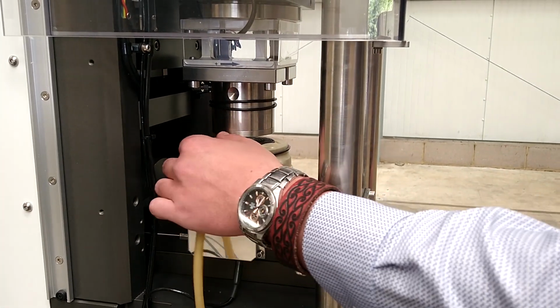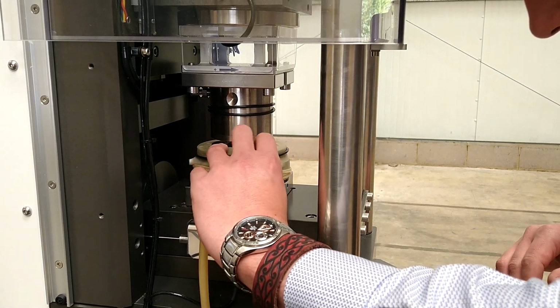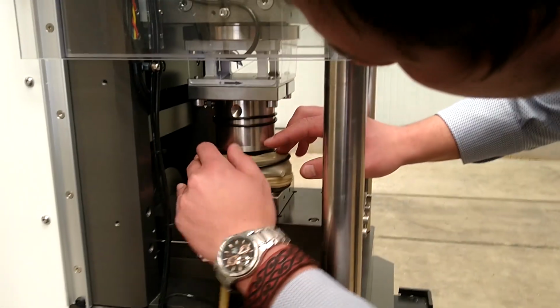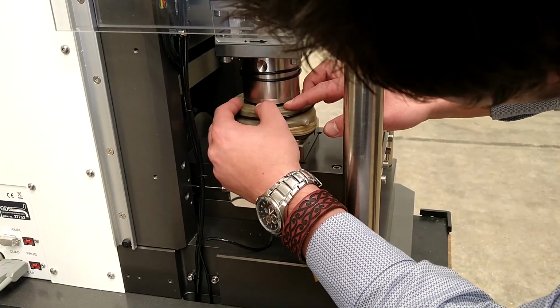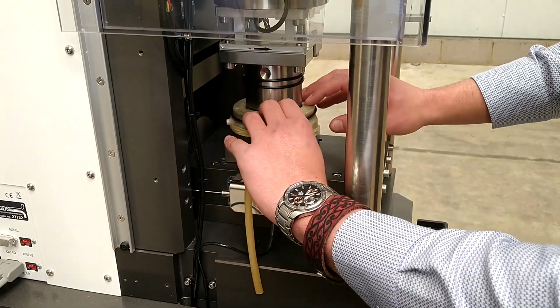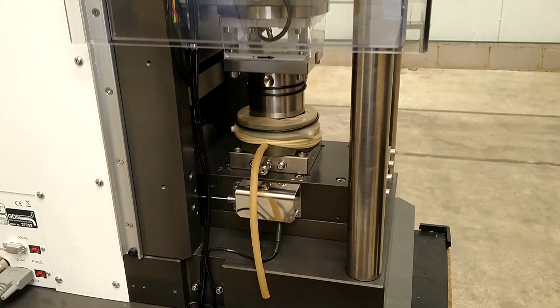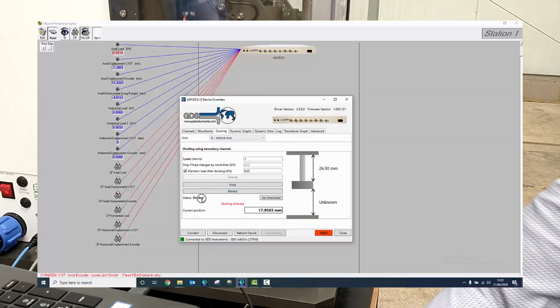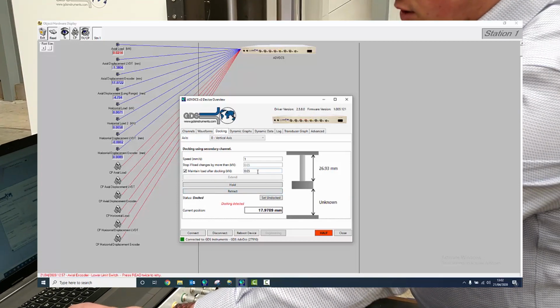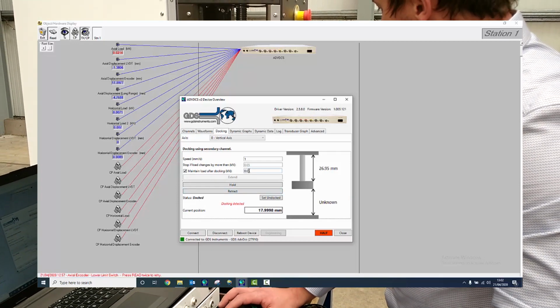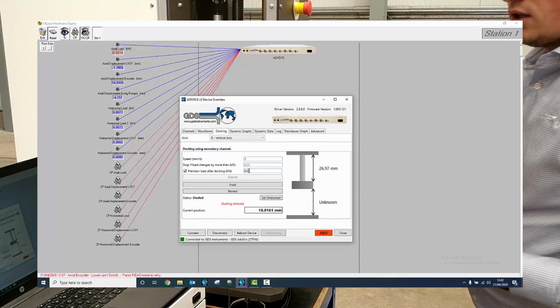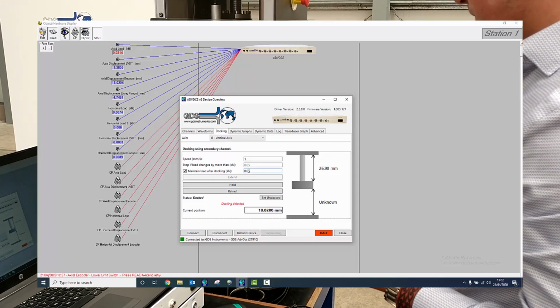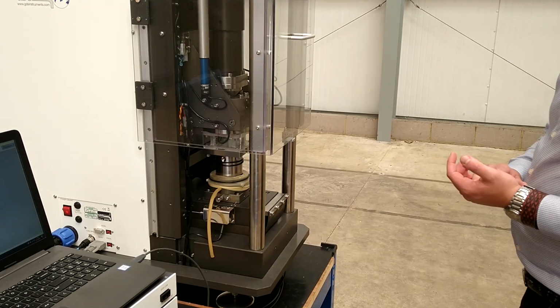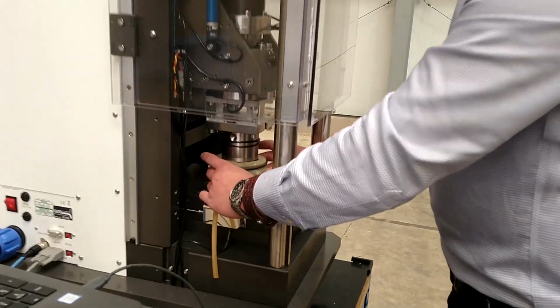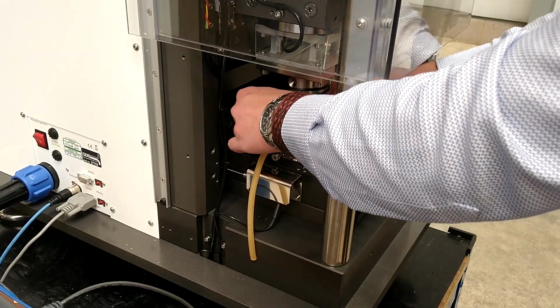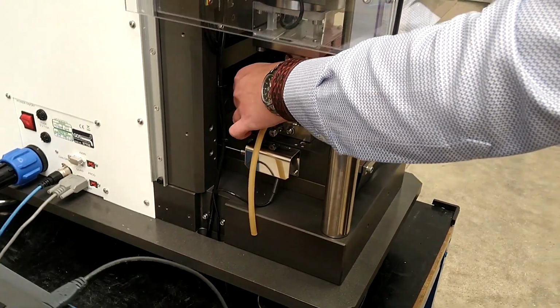At this point, it's worth just double checking you are not catching any membrane between the sample and the disc, just to make sure you're docking purely on the sample. And as you can see, the status in the window has changed to dock, which means the machine is now in the control of the load, targeting the constant small docking value. So now we can actually flip the membrane and take off the vacuum former and actually prepare the test.